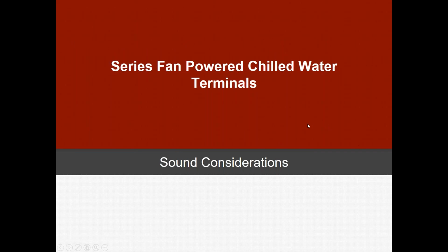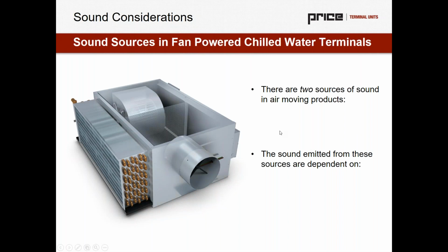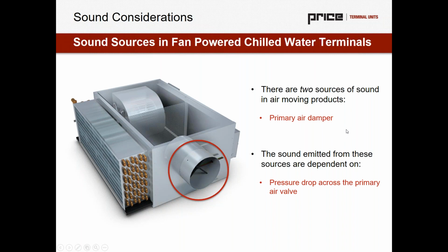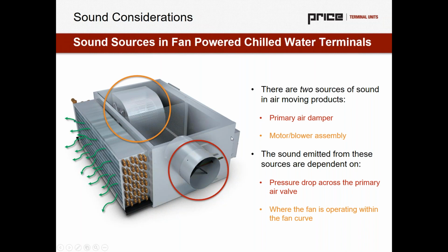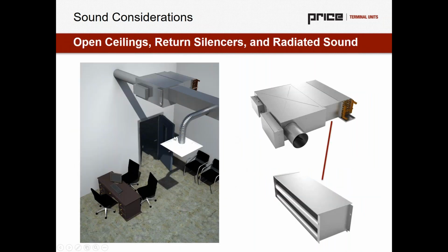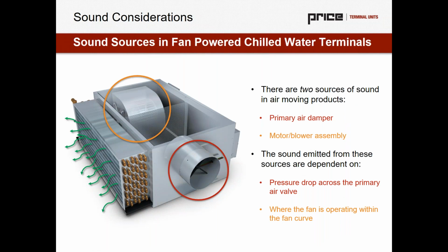So next we're going to look at acoustics here briefly, which I think is a great opportunity for chilled beams in particular to kind of shine in this hybrid application. But first I just want to glance quickly at this fan-powered terminal unit again. And the thing that's really noteworthy here is the fact that there's two different sound sources. So we have that primary air damper and that motor blower assembly, both of which are generating noise. But most critically, we have this large coil on the side of the equipment, which is essentially just operating as, you know, a hole for sound to travel through. Sorry, skipped over that a little bit briefly. So it's really operating as a hole for sound to travel through, which is a design constraint.